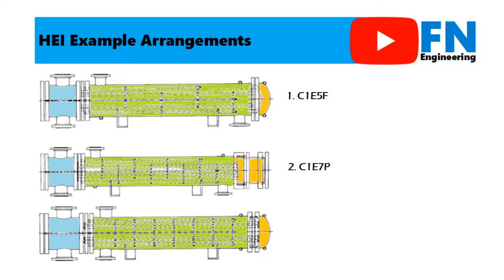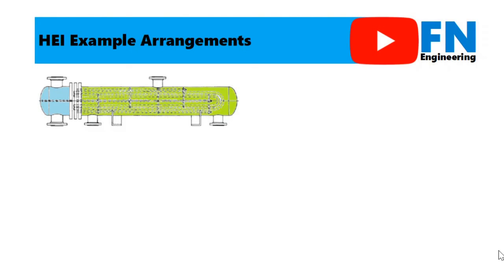The last example: the front head is the bolted cover, the gasket on both sides, the shell arrangement is two pieces, the stationary tube sheet uses lantern ring and peg both sides, and the rear head is bonnet cover. So the heat exchanger in TEMA type is C1T8P.